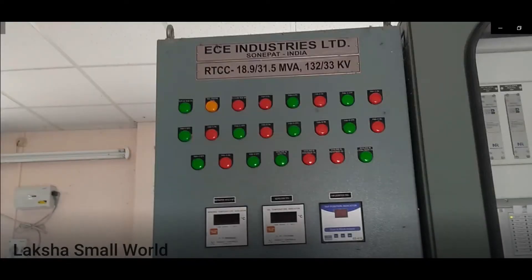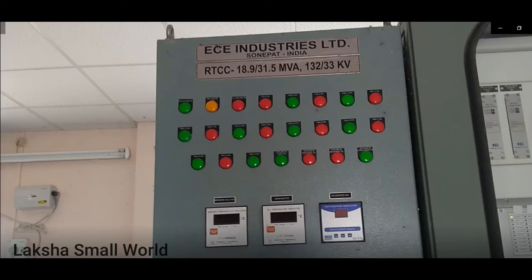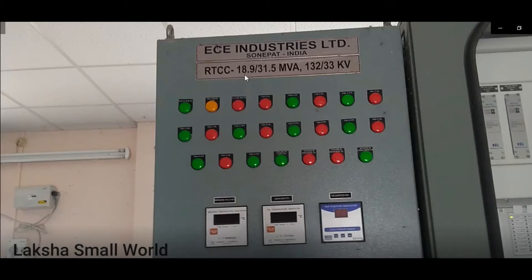Now let us move on to the control panels of the transformer. Basically the transformer has three control panels: one is RTCC (remote tap changer control), the second is the HV side control panel, and the third is the LV side control panel. Here you are seeing the RTCC control panel. From this panel you can find the transformer ratings — 18.9 MVA when cooling is oil natural air natural, and 31.5 MVA when cooling is oil natural air forced.